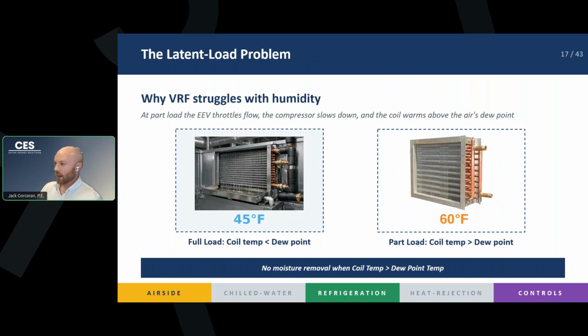So another caveat of VRF systems is the way that they vary the pressure, right? If your valves are opening and closing, you're varying the pressure in our systems. And as we said before, that actually changes the temperature of our coils. So if your full system is mostly meeting its demand, right? Most of the zones' temperatures are satisfied. Then our compressor starts to slow down because all of our EEVs are starting to close. The consequence of this is that we're not changing our pressure as much and we're not getting as much temperature change. So when we're running at full load on the left side, our coil temperature is quite cold, right?